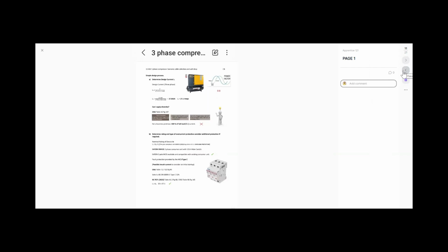Within the compressor, of course, is a motor, and other than a lift motor, we can't apply diversity, because it's saying for a business premises, we've got to take 100% of the full load current of the largest motor. Because it's the only one in there, we'll assume we can't apply diversity. So design current is 27.1 amps. Happy with that? Yep, I'm more than happy with that. Makes perfect sense to me.